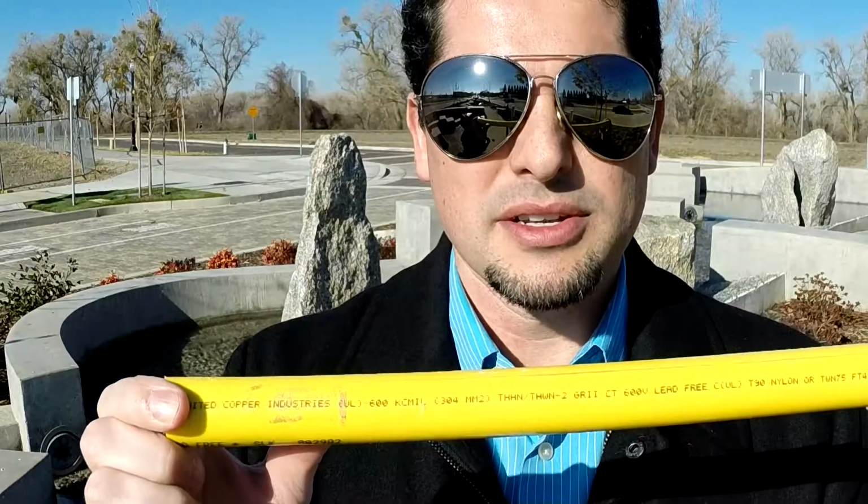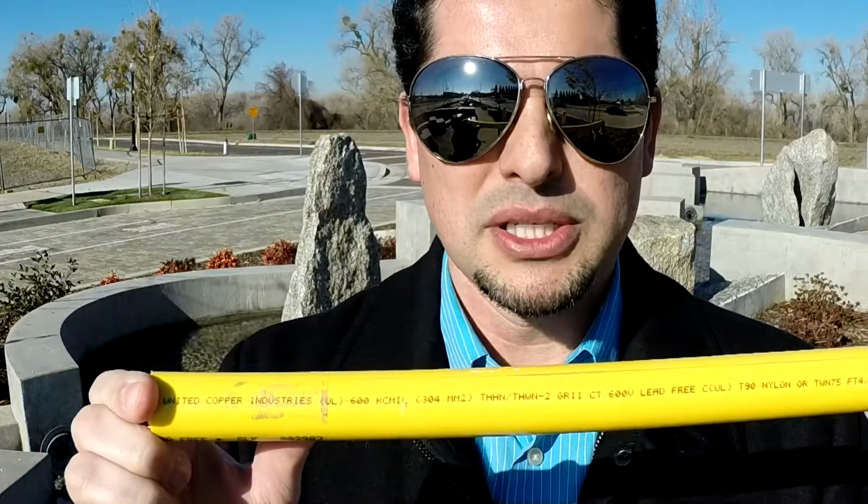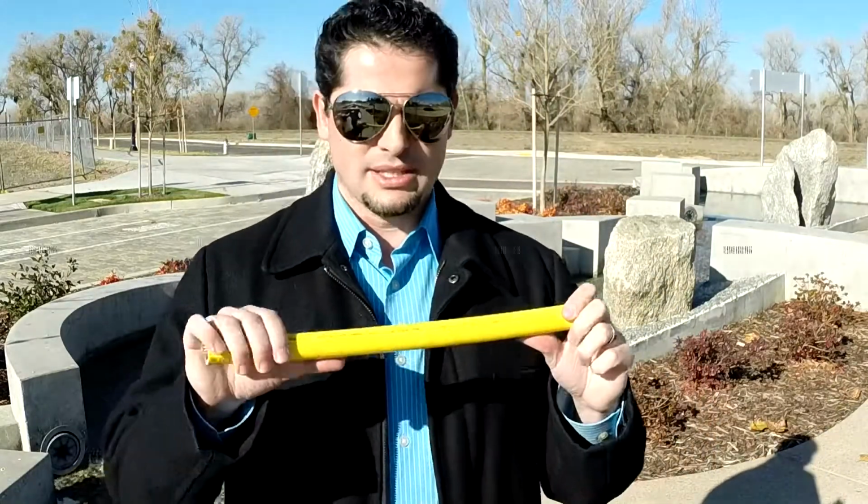So that is why there is no ampacity rating printed right on the cable. If somebody tells you a certain cable has a universal ampacity with no follow-up assumptions, you need to ask yourself some questions, and you probably need to ask them some questions too. And you should be very wary of anybody who states universal ampacities for certain cable sizes and types. I hope to get into more detail on the more advanced levels of how you calculate the ampacity of cable for different situations.